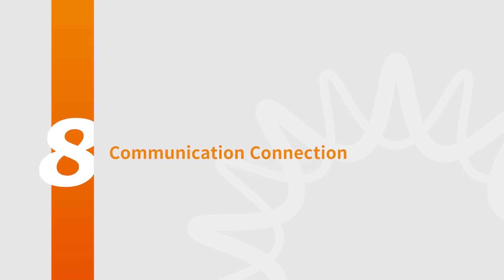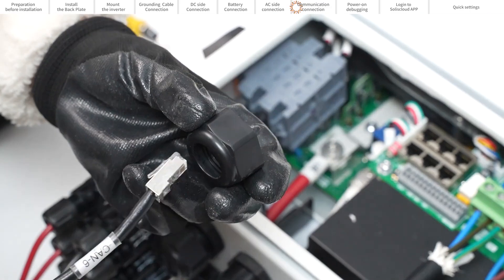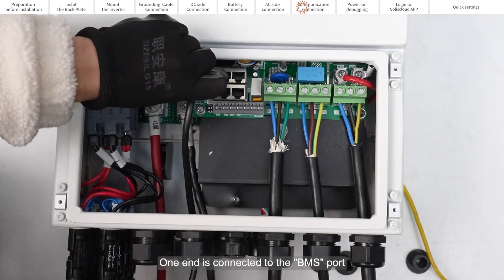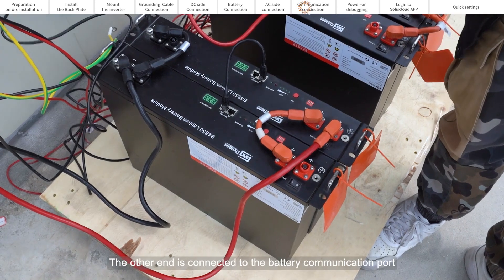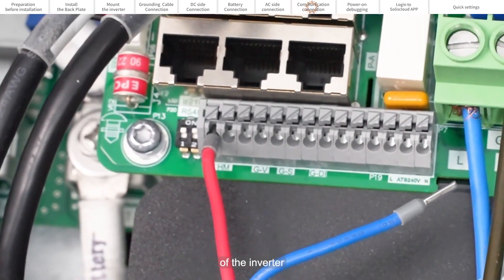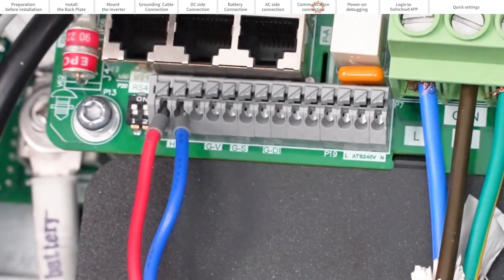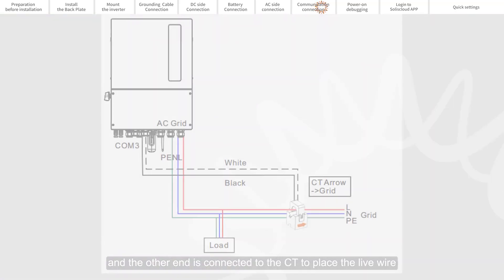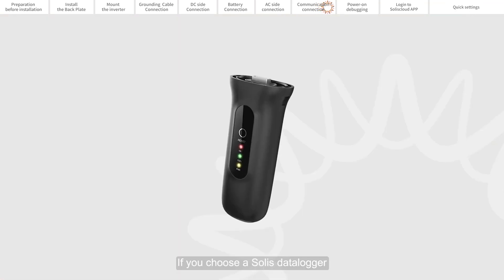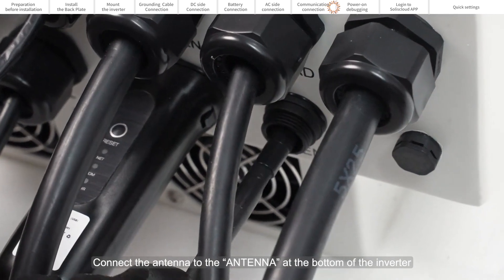Part 8: Communication Connections. Thread the communication cable through the COM port on the bottom of the inverter. One end is connected to the BMS port and the other end is connected to the battery communication port. If only CT is connected, the communication wire passes through the COM port at the bottom of the inverter; the other end connects to the meter, and the CT is placed on the live wire. Close the protective cover and tighten the four screws. If you choose the Solis data logger, connect it to the COM port at the bottom of the inverter and connect the antenna to the antenna port at the bottom of the inverter.